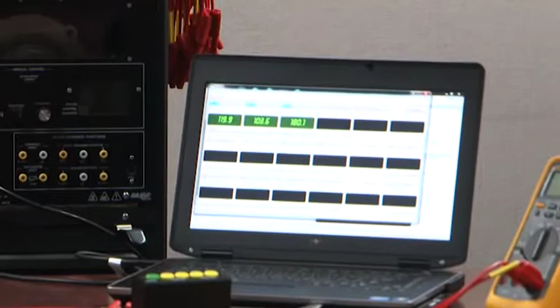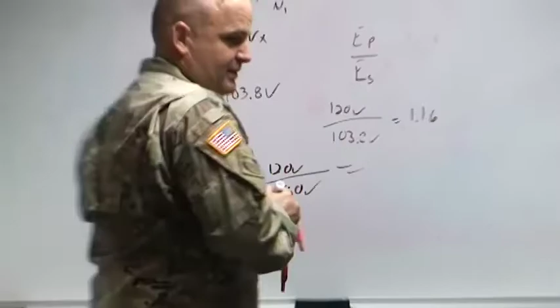So now, tapping off the same setting, I'm still tapping off a 3, but now I'm referencing 8 instead of 7. I've got V primary, 120 volts, over V secondary, 180 volts. The ratio between those two points, I believe that's 2/3 or 0.67.